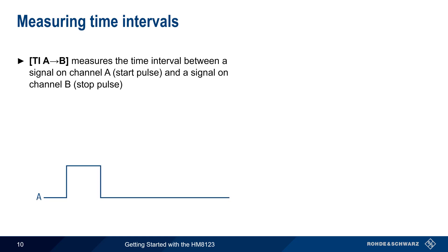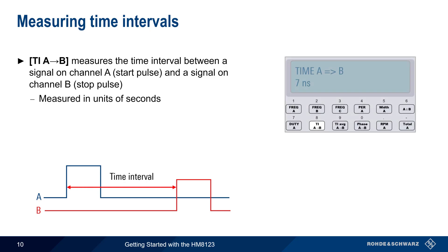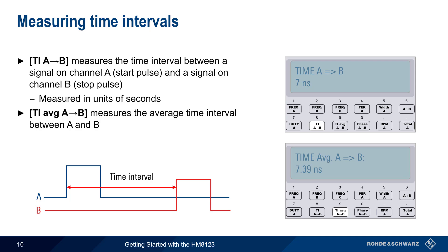Another type of two-channel measurement is time intervals. The TIAB key is used to measure the time interval between a signal on channel A, defined as the start pulse, and a signal on channel B, or the stop pulse. This is measured in units of seconds. The average interval can be calculated and displayed by pressing the measurement key TI-Average AB.